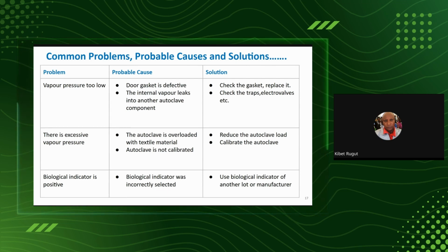If you also have excess pressure, say you set up some pressure, maybe 30, 40, or even a higher PSI, if you are using PSI, and you are always getting your gauge reading higher, it means there is a sensor that is compromised. It cannot sense the right pressure, so it is still urging the autoclave to boil more. The problem could be that you are overloading with a lot of textile material, and your autoclave is not calibrated. In other words, your vapor pressure reading gauges should match the set pressure switches. So first you calibrate, and then you reduce the autoclave load again.